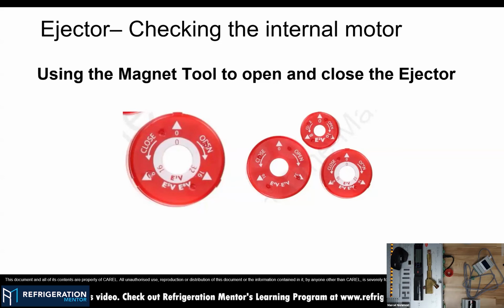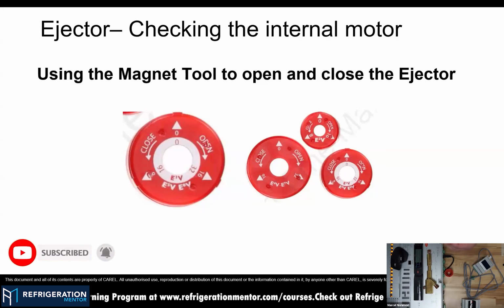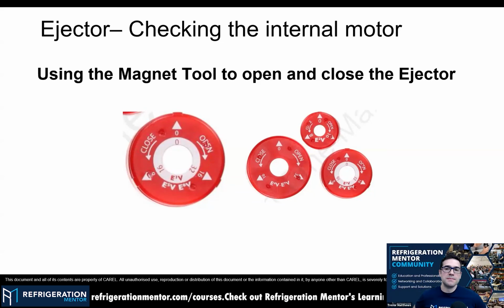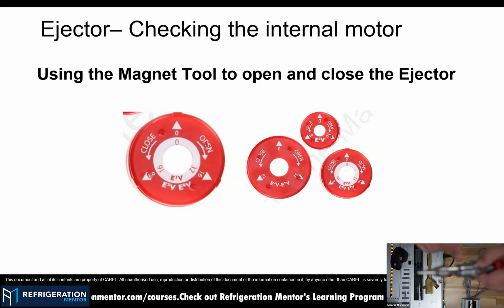So if you arrive at a place, you have your magnet, and you keep listening for the clicks on both sides without moving the ejector, it means that the motor is stuck inside, and most probably you will need to replace it or at least open it for cleaning. Another good point is that you can see here we have two O-rings, and every time you decompress them, the O-rings tend to dilate and will not fit and make the seal again. So every time you open a valve like this, it's highly recommended to replace the O-rings with new ones so you can maintain the seal inside the components.